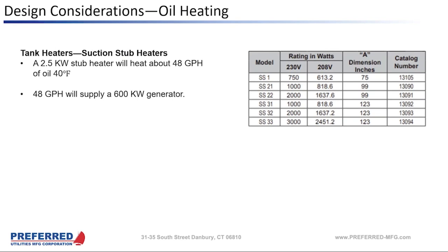A word about tank heaters. So a suction stub heater, our 2.5 kW version will heat about 48 gallons per hour of oil up to 40 degrees F. And 48 gallons per hour will supply a 600 kW generator. So you can see on the chart on the right, we offer a bunch of different sizes, and this just gives you an idea of how many kW it's going to take to run a suction stub heater. And really, 2.5 kW is not a lot of electricity compared to some other methods that we're going to show you later.